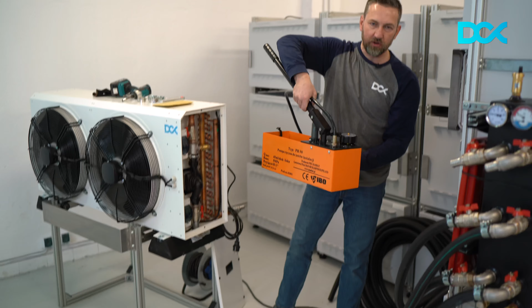So let's follow up on the filling procedure of the ICP40, how to start up the system, how to commission it. You will need just one tool actually to do that, which is the filling pump. One of those units, which we also deliver with the package. As you can hear, it's full of water, and that unit will be connected to the one-way valve, which is used for the filling process.